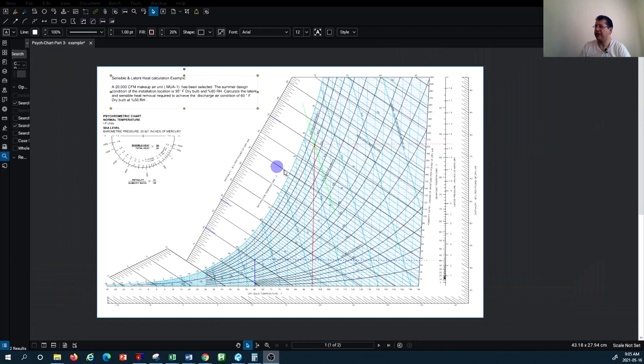In order to perform this calculation, there are two methods. The first is through getting the enthalpy at the starting and ending points. The second option is to separately calculate the sensible load and the latent load, then sum them to get the total load. There may be a slight difference between the two methods, but it will be fairly negligible.